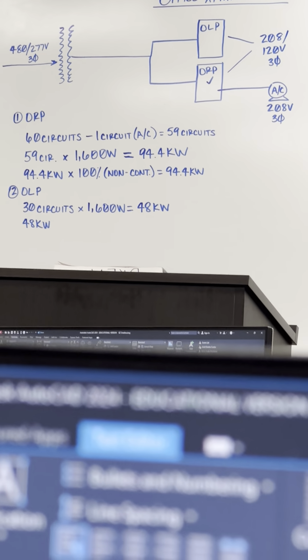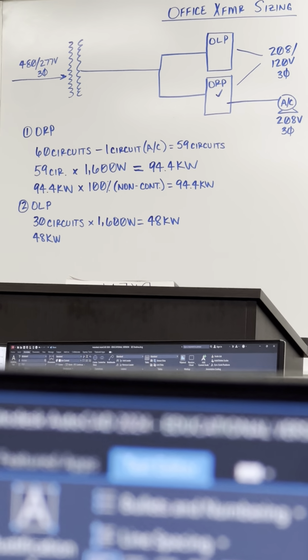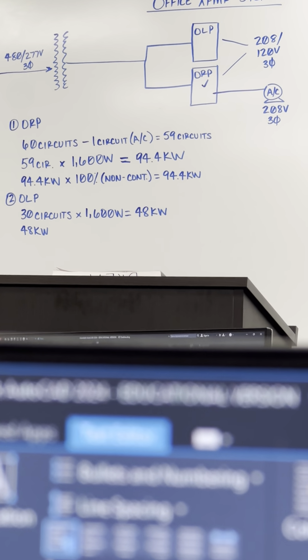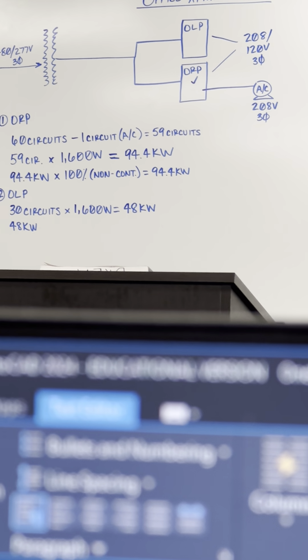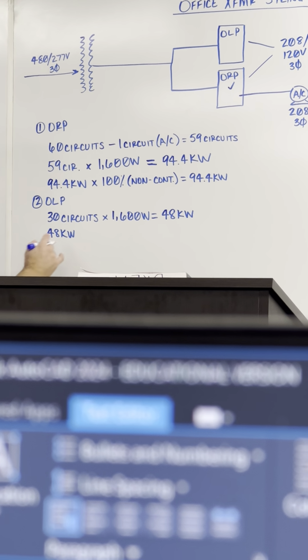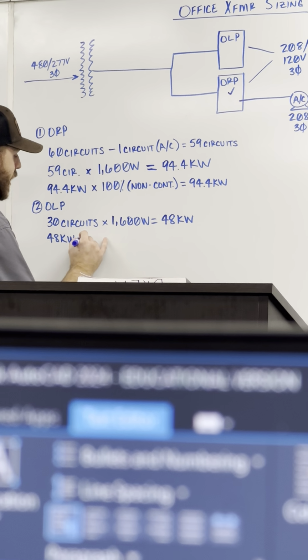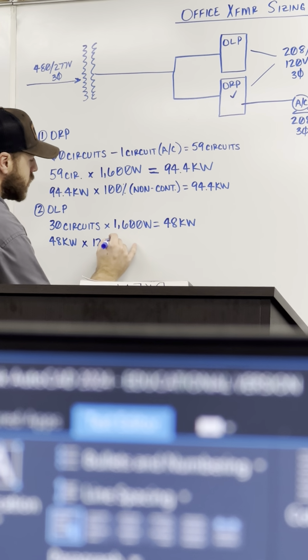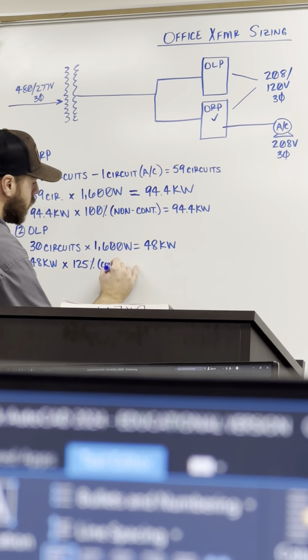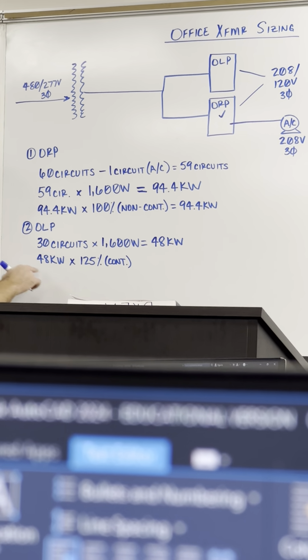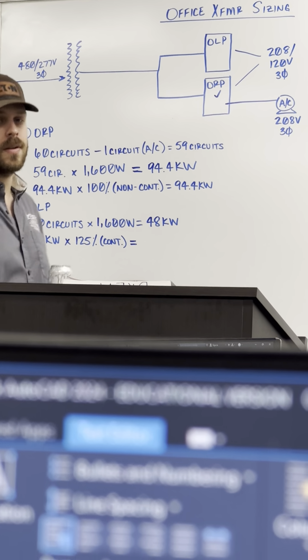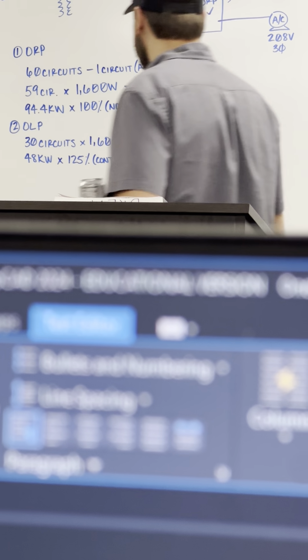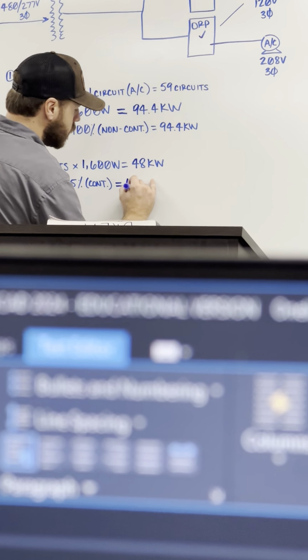So even street lights at the utility company are considered continuous there, right? So you walk into a building, or street lights at night, they're running for 3 hours or longer most of the time. So we're gonna show that by taking 48 kilowatts times 125%. Very similar to our motor circuits there for continuous load. And that will change our answer. And I get exactly 60 kilowatts. So that kind of takes care of our lighting load.